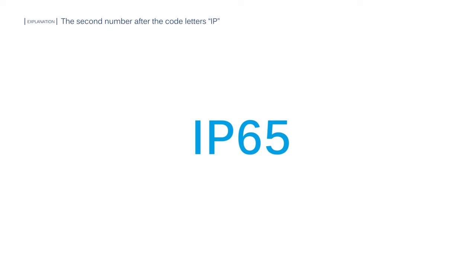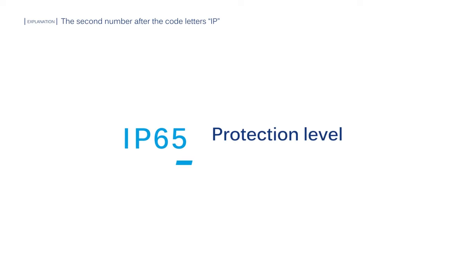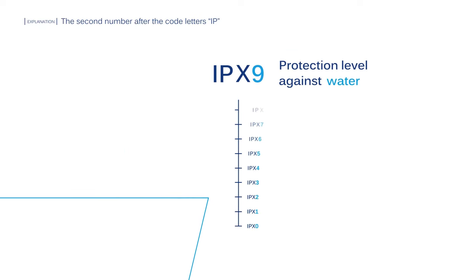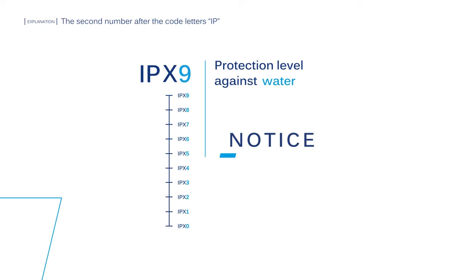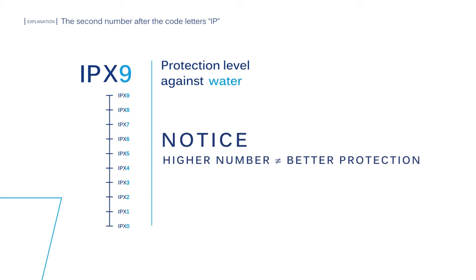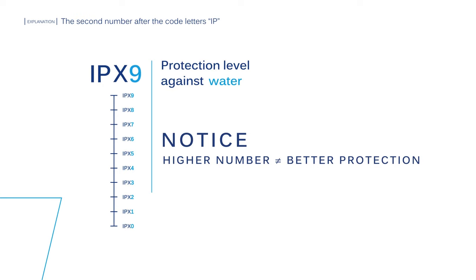The second number after the code letters refers to the level of protection against water. The levels go from 0 to 9. It is important to notice that in the case of protection against water, a higher number doesn't automatically mean better protection, like it does with the first numeral.